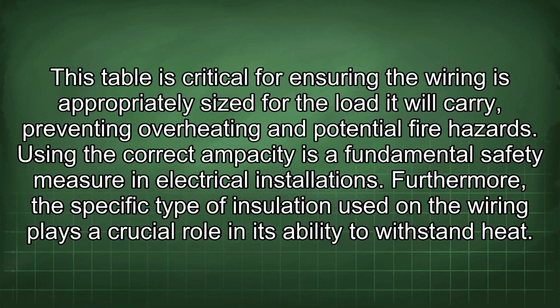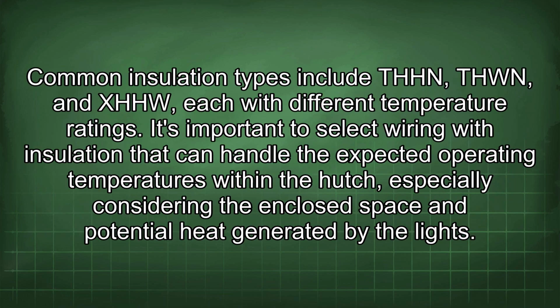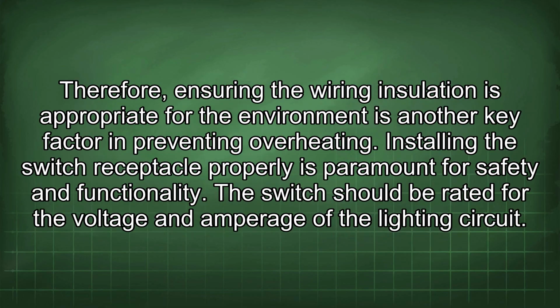Furthermore, the specific type of insulation used on the wiring plays a crucial role in its ability to withstand heat. Common insulation types include THHN, THWN, and XHHW, each with different temperature ratings. It's important to select wiring with insulation that can handle the expected operating temperatures within the hutch, especially considering the enclosed space and potential heat generated by the lights. Therefore, ensuring the wiring insulation is appropriate for the environment is another key factor in preventing overheating.